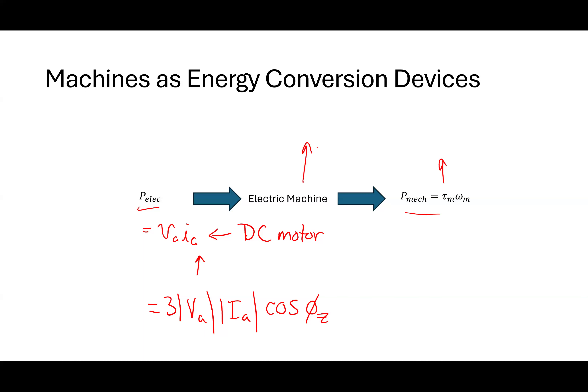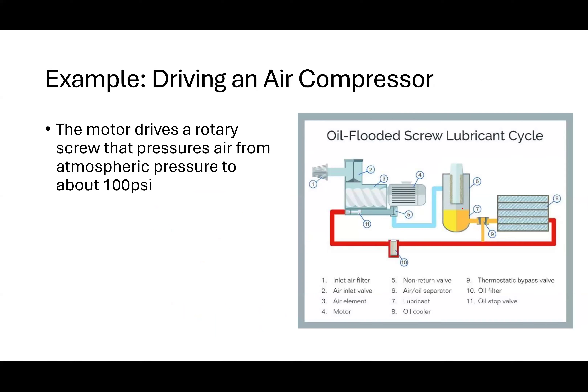Typically there is some efficiency to a motor. This one-horsepower motor is probably not particularly efficient, but if I get a large enough motor — usually 10 horsepower or more — I might see 95% efficiency. So if I'm delivering 10 horsepower at the shaft, the input power would be one divided by 0.95 times that. Where would you be losing power? At least two reasons: friction on the shaft and bearings, and resistance inside the machine — currents have to flow inside of it.